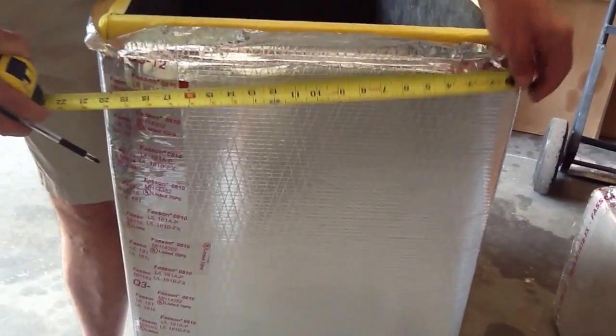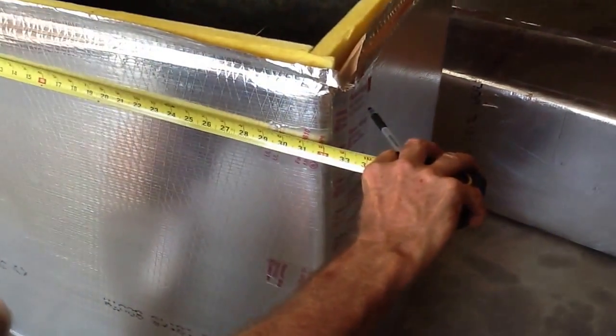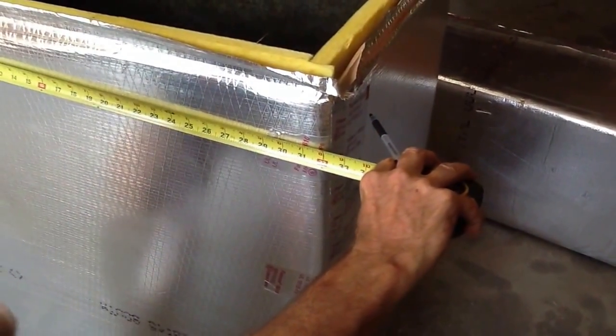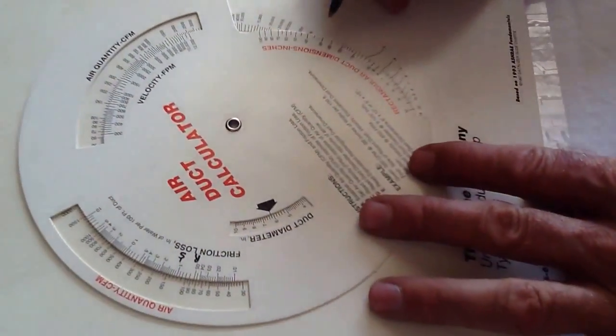We're just going to round it up to 20 inches by 32 inches. Now the thing you want to do, because this is inch and a half duct board, we have to reduce three inches because the inside dimensions of this duct work is not 20 by 32. So we want to go down here on our chart...